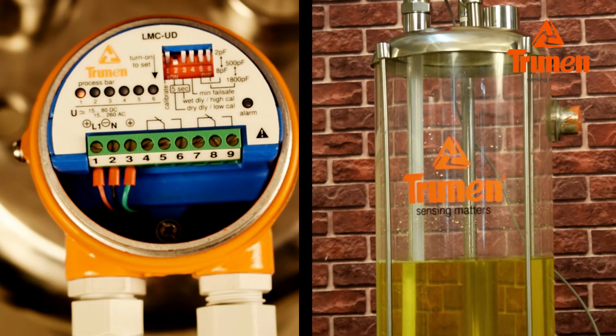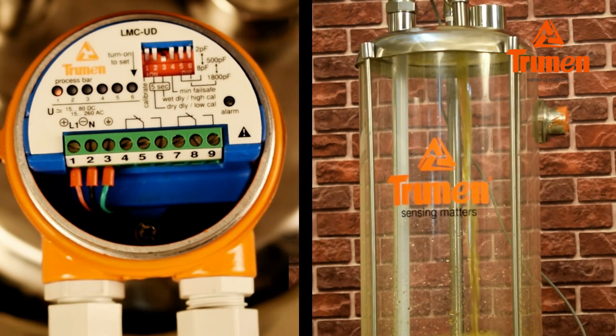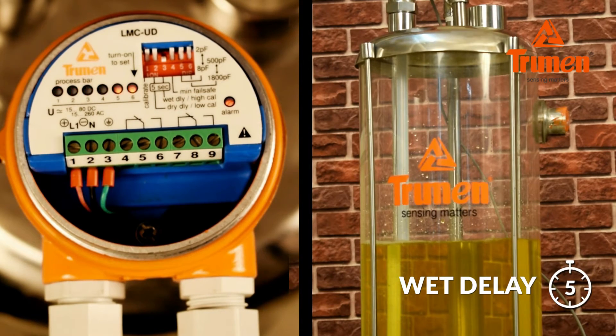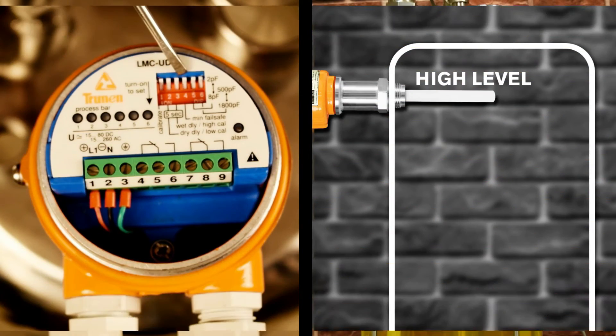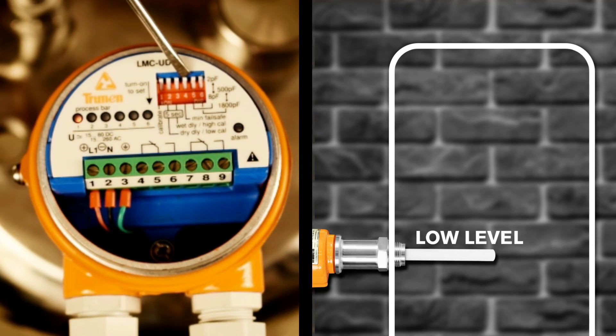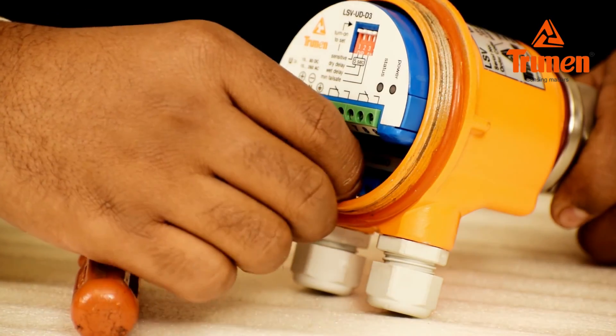During the delay cycle, the sensor avoids turbulence. Switch three sets wet delay — an on delay — where the LMC waits five seconds once material touches the sensor before generating switching, also avoiding turbulence. Failsafe is set via DIP switch four: when the probe is installed for high level, keep switch four off (failsafe maximum); when installed for low level, keep switch four on (failsafe minimum). You can easily replace the electronics module as shown.